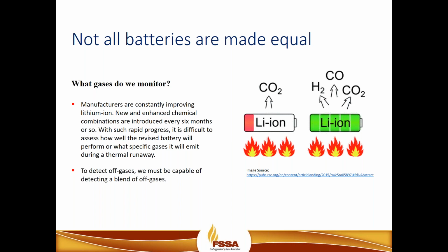Also, traditional technology that we have on the market today, such as fixed type sensors, is challenged to detect at the lower level limits, which are required for off-gas monitoring. For example, if you were to use an LEL detector to detect carbon monoxide off-gassing, maybe at 25 parts per million in that particular scenario, the LEL detector wouldn't be able to detect at a low enough level to prevent or stop the abuse factor and prevent thermal runaway from occurring. So we need to use a sensor that can detect at the very, very low levels required, the lower limits that are required in the off-gas concentration levels.